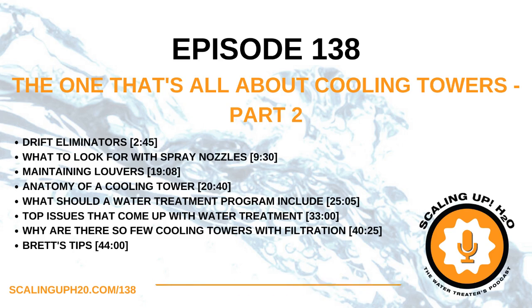The modern drift eliminators can be as low as 0.0005%. To calculate how much drift you have, you would take the 0.0005% and multiply by the recirculating rate. So whatever that condenser water pump is recirculating the water at, to get the drift you would see out of that tower. That 0.0005% is as low as you can get on counterflow type cooling towers.